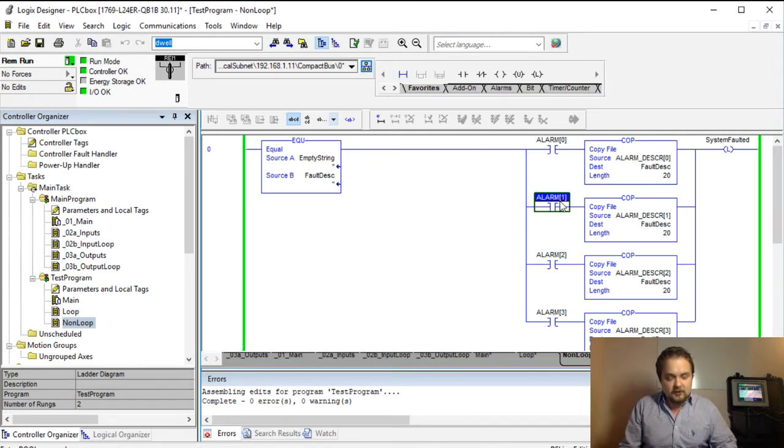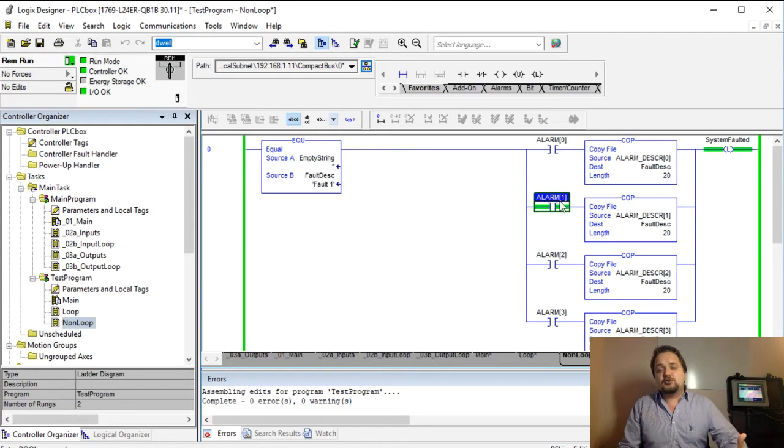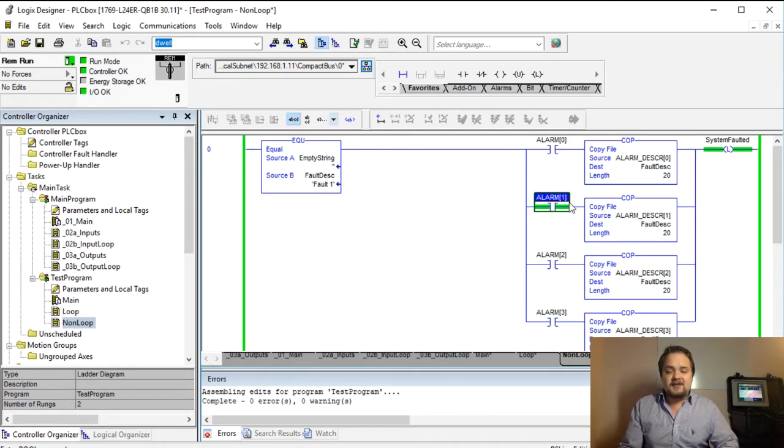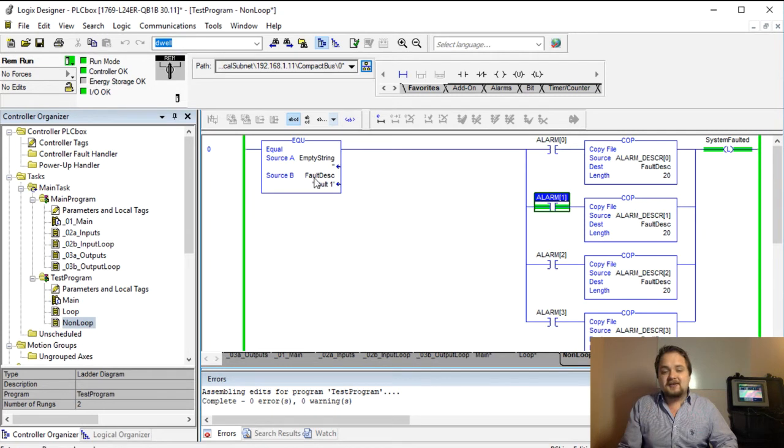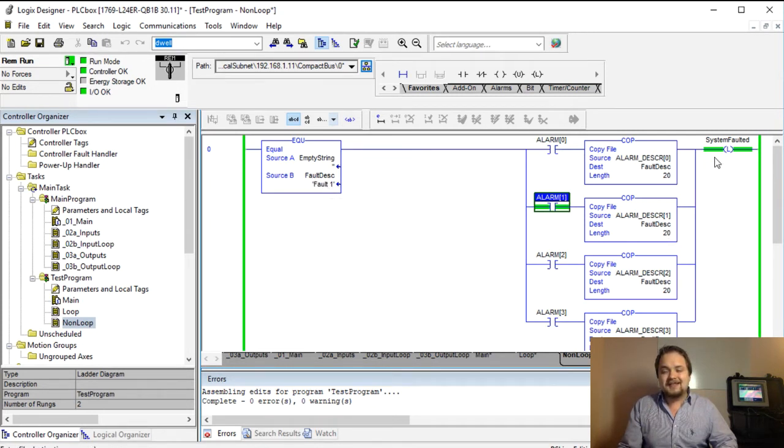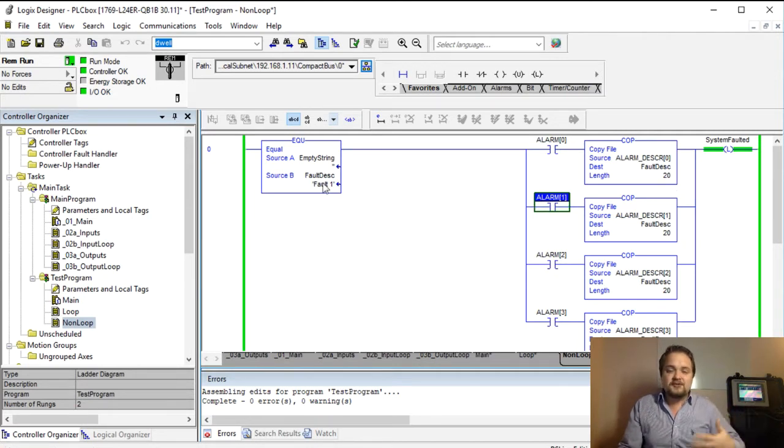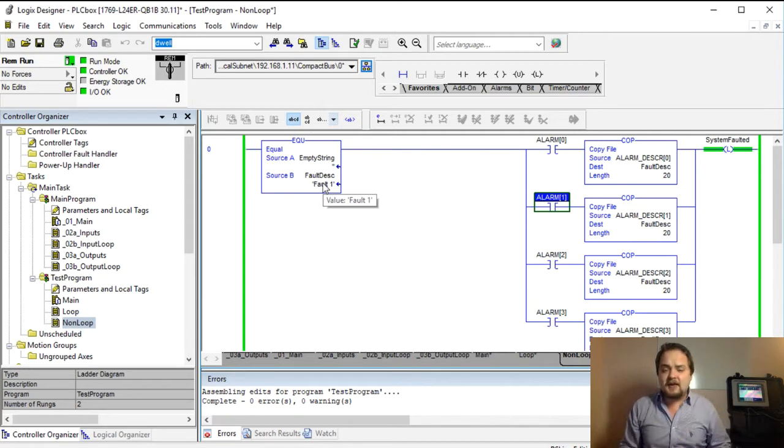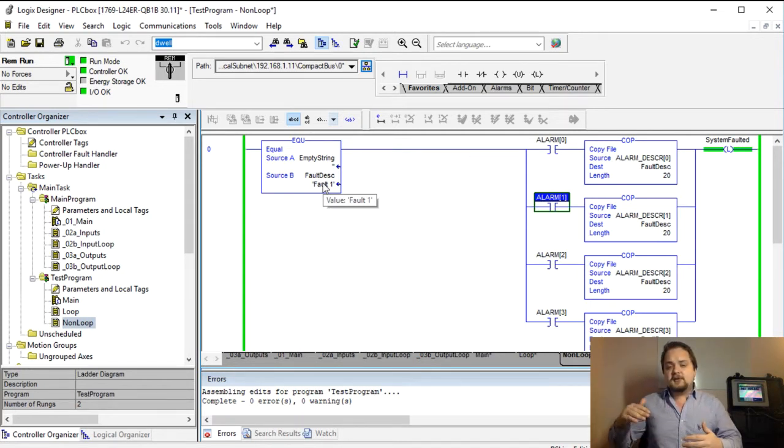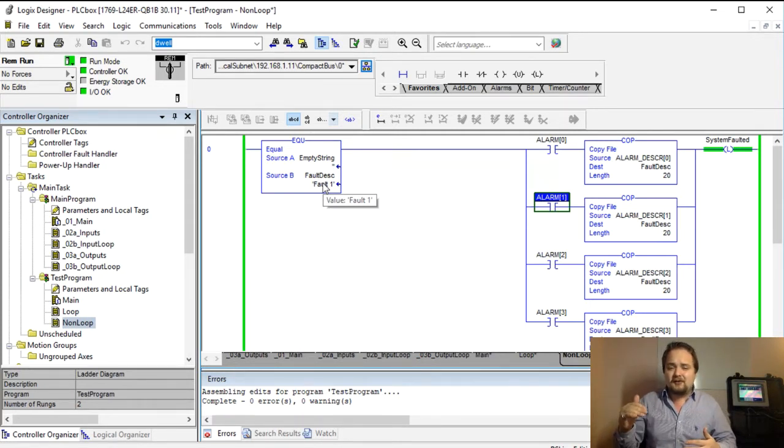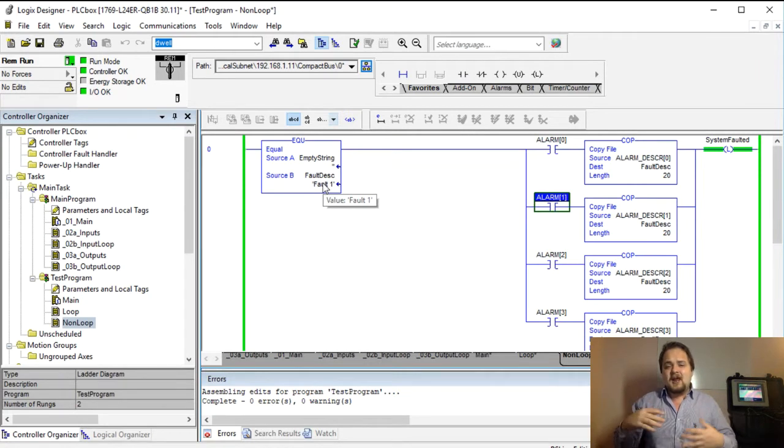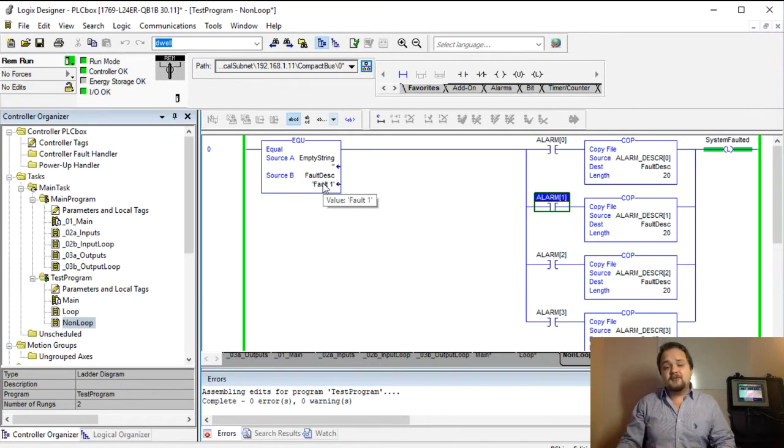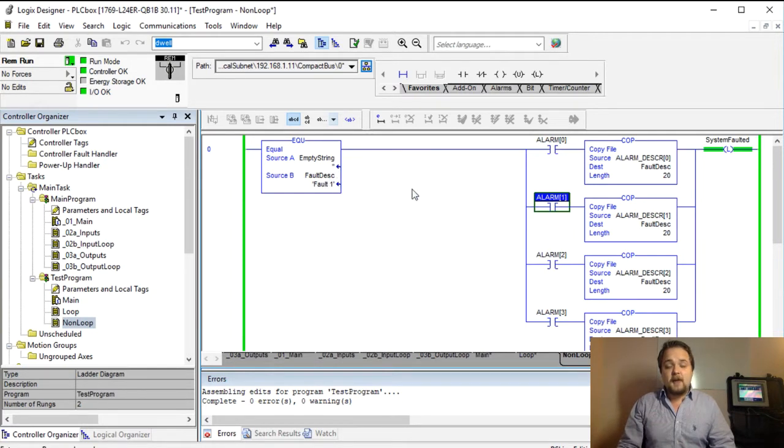But let's say alarm one is triggered so I'm just going to control T which triggers that particular bit and so for example you have an over temp, this becomes active as you can see the current fault description is going to be fault one and the system is faulted. Of course if you go below the temp you still have retained the fault description because what you want to prevent from happening is somebody you know for example the temperature goes up and then it goes down for whatever reason and then it clears the fault automatically. So you've essentially captured the fault and you're able to see it in your fault description bit.